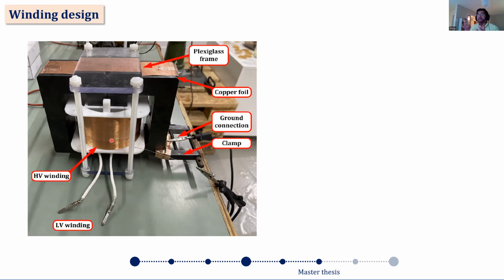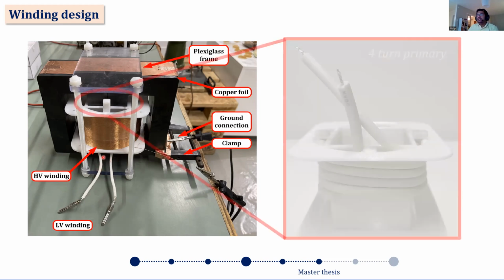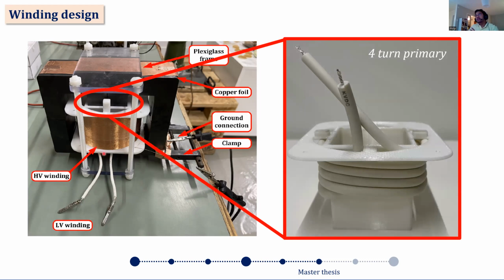But finally we somehow made it work like this. Also, the highest potential from HV to low voltage was a very severe design failure. So what I essentially did was concentrate the LV winding towards the bottom and kind of invert it, and use a silicon insulated wire instead. This was my 4-turn primary, essentially concentric to the high voltage winding.